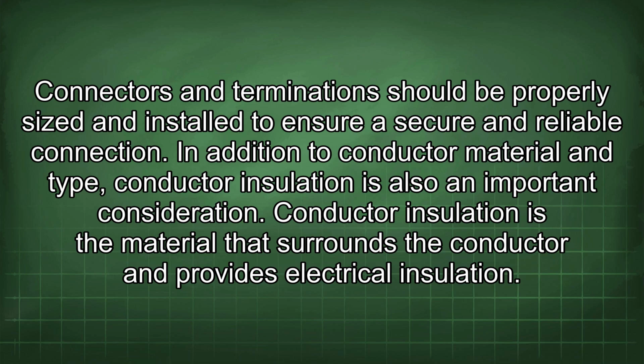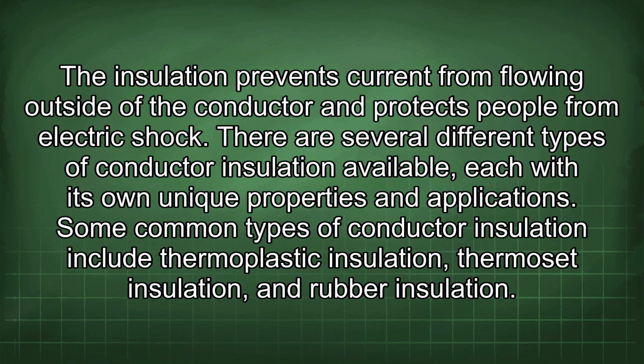In addition to conductor material and type, conductor insulation is also an important consideration. Conductor insulation is the material that surrounds the conductor and provides electrical insulation. The insulation prevents current from flowing outside of the conductor and protects people from electric shock. There are several different types of conductor insulation available, each with its own unique properties and applications. Some common types of conductor insulation include thermoplastic insulation, thermoset insulation, and rubber insulation.